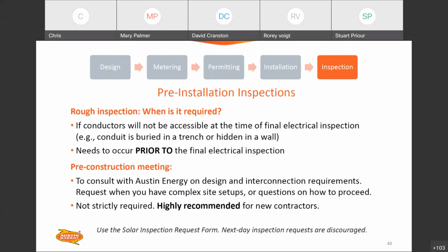But there are several types of inspections you can use that request form for before you complete the installation. For instance, rough inspections are required if conduit will be hidden before the final inspection occurs. So if you're going to bury conduit in a trench or hide it in a wall, make sure you call for a rough inspection through that request form so our inspectors can come out and look at that conduit before it's hidden.